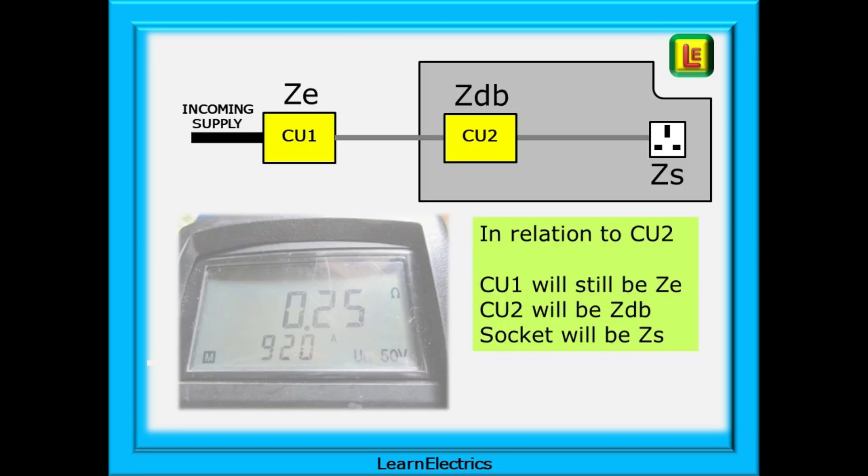Looking at a simplified view of CU2 now, and CU3 will be the same, CU1 is still ZE, the only ZE, and this will be the intake or supply ZE on CU2 paperwork. We put ZDB on the CU2 schedule of test results, and ZS for the socket that is on CU2. This ZS is ZDB plus R1 plus R2.